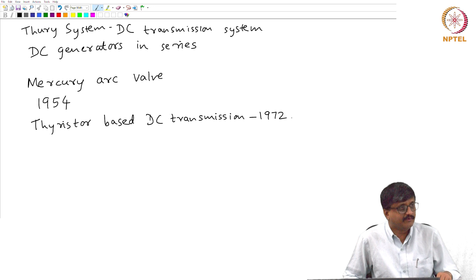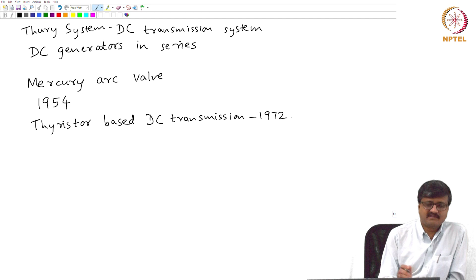So there were many HVDC transmission lines using mercury arc valves. The very first DC transmission line was in 1954, using mercury arc valves. Now the thyristor based transmission started only in 1972. So from 54 to 72, a large number of converters were commissioned using mercury arc valves. Of course, there was a mercury arc valve based converter which was working till 2011. As of today, there is no converter using mercury arc valves. So either we have thyristor based or the more advanced ones which are voltage source converter based.